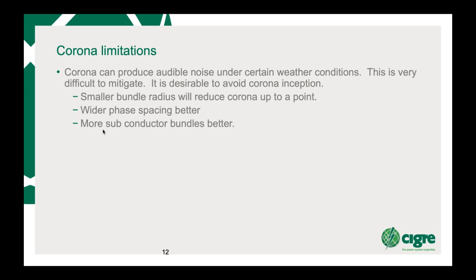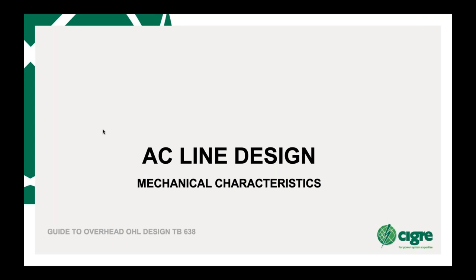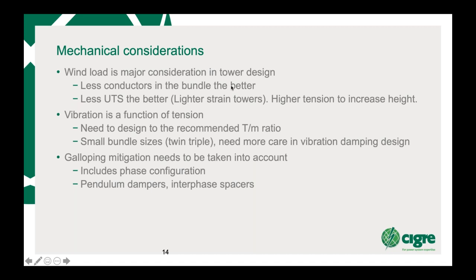Now we look at the mechanical characteristics of AC line design. When you're looking at mechanical characteristics, wind load is a major consideration. And what does it state there? Fewer conductors in the bundle is better. Now, when we looked at corona, it said more conductors in the bundle is better. Also, less UTS is better. You get lighter strain towers, and you can use higher tension to increase the height, so you can use lower towers, so you can get a saving with conductors with lower UTS. In other words, conductors that are not that strong, as long as you can manage the ice and wind loading.